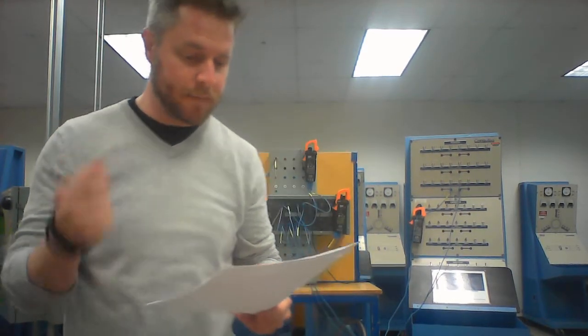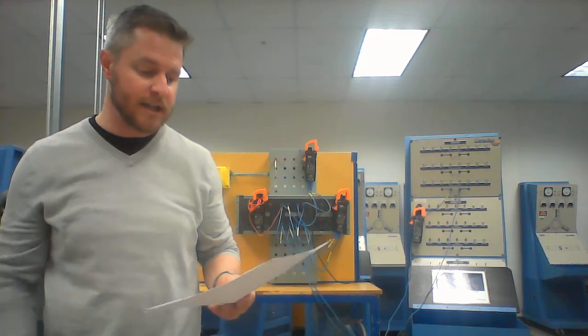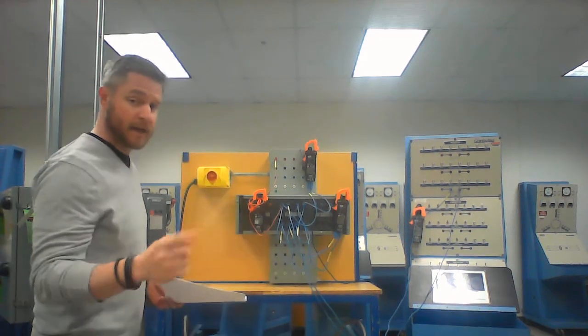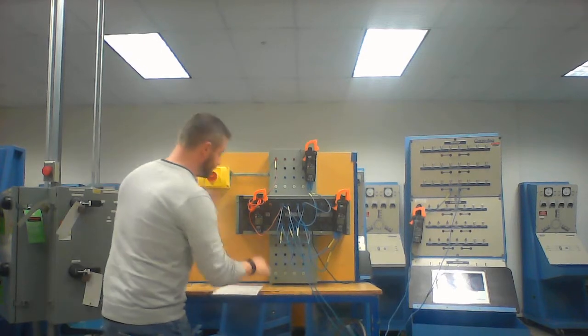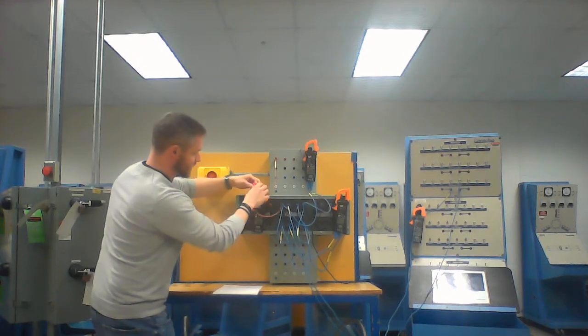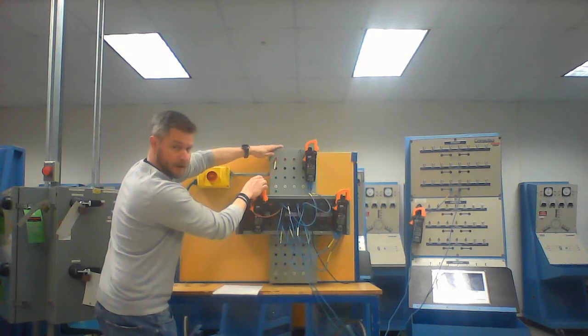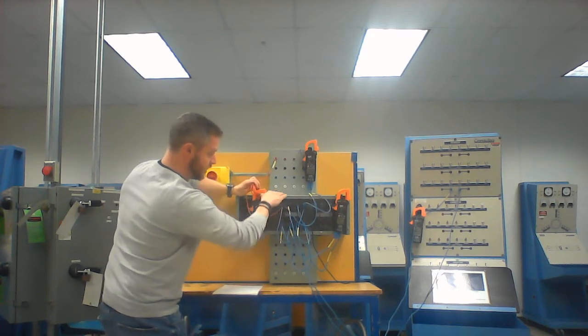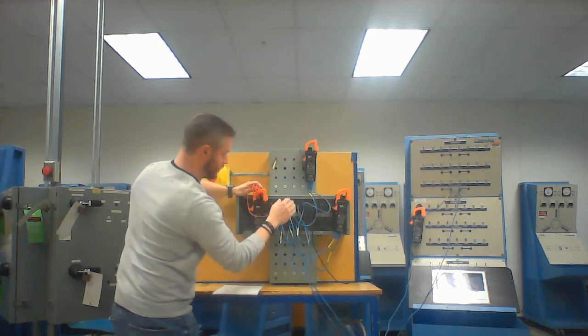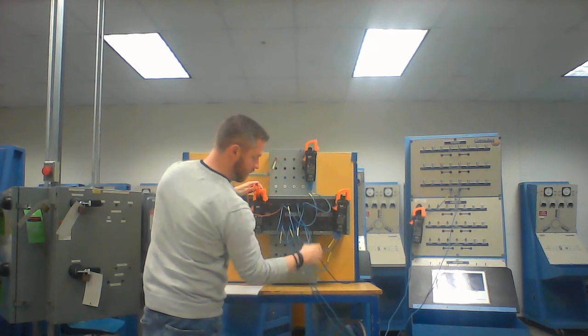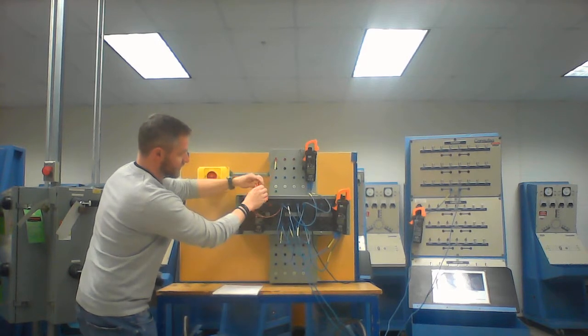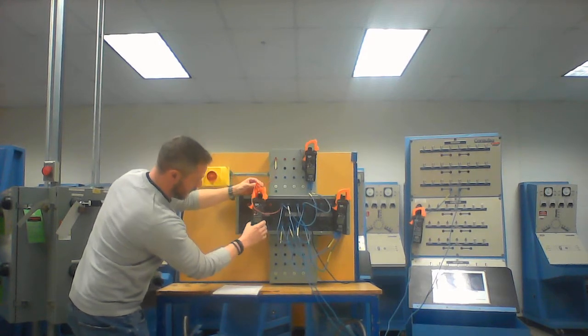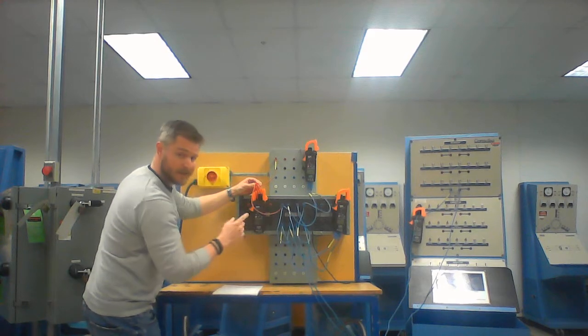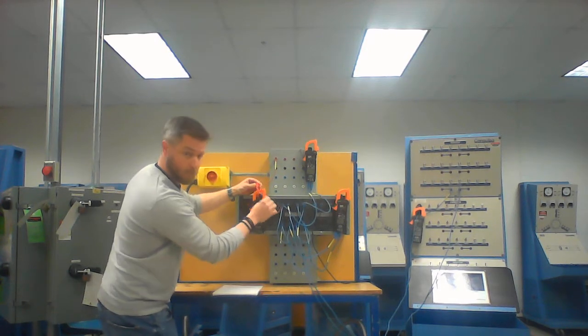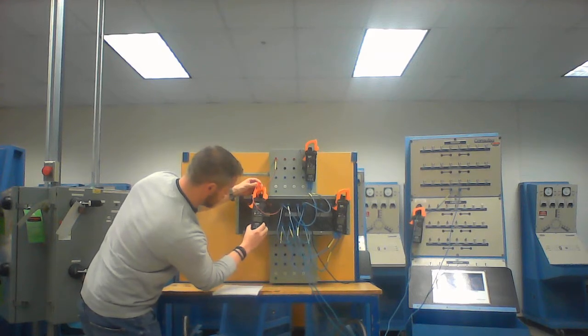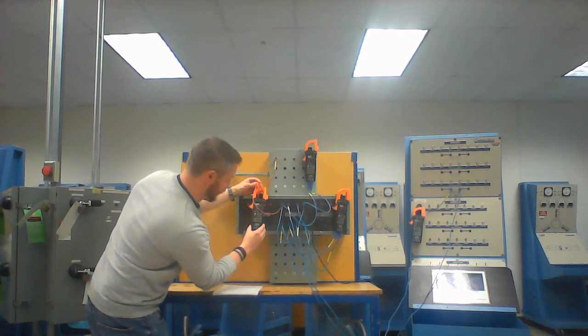Part number 3 says turn on the power and measure and record the current. This is the excitation current. You're going to do this again next week, but I'll show you why I'm doing it right now. This meter here is reading excitation current right from my source, right from my supply up top here. And all it's doing is feeding the EMF in the transformer to get juices flowing and output my 120 volts on the secondary. What I've done is I put a 6-turn coil through that meter, so whatever value I see on this meter, it actually reads 6 times greater the current of 1 wire. So at this point in time, I read 0.65 amps.